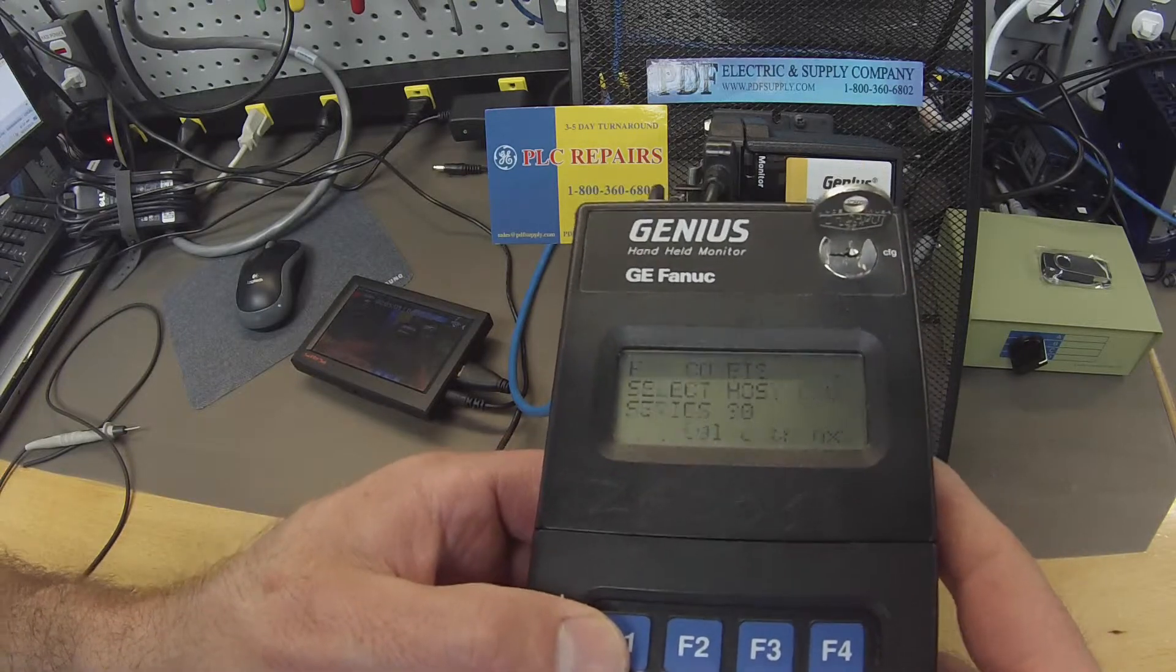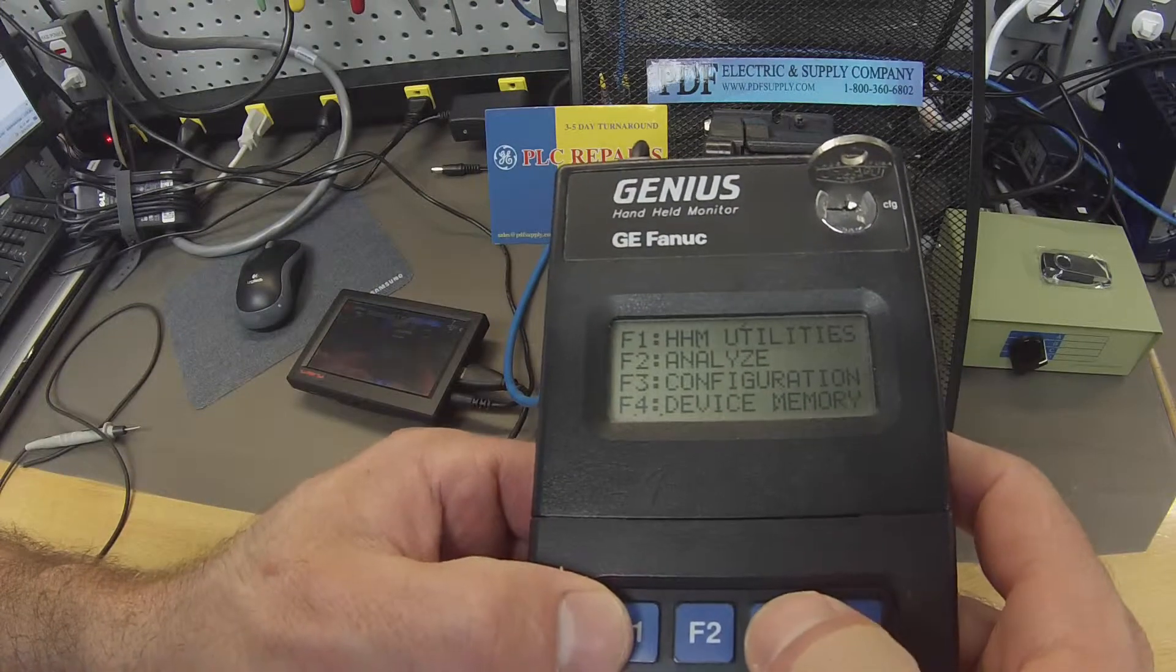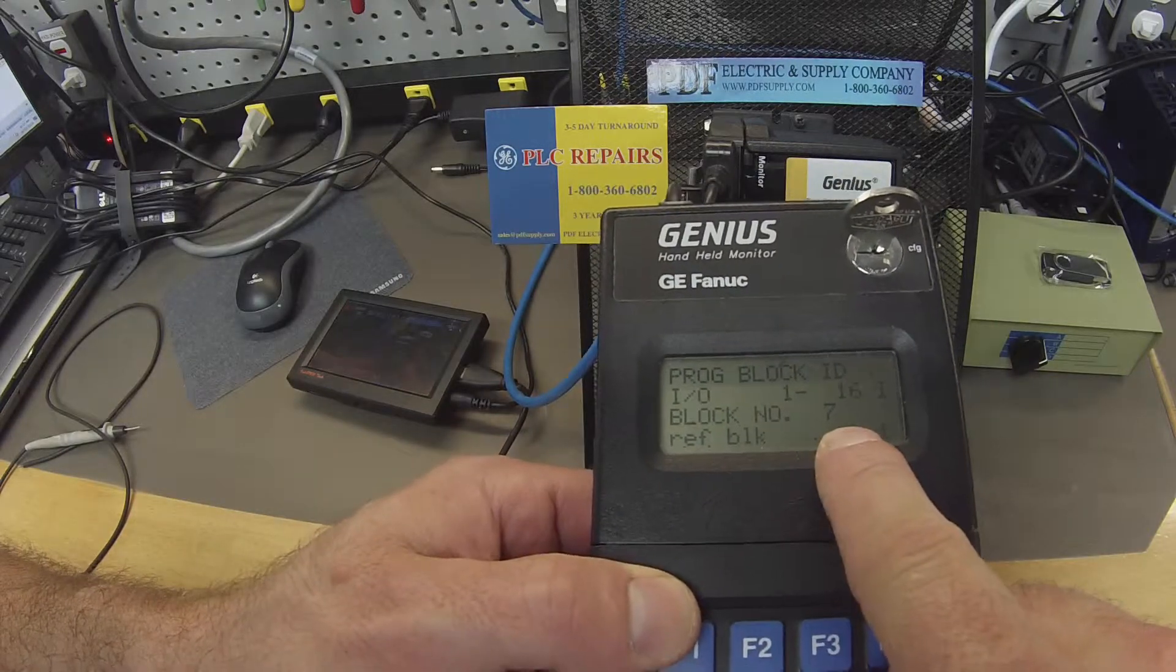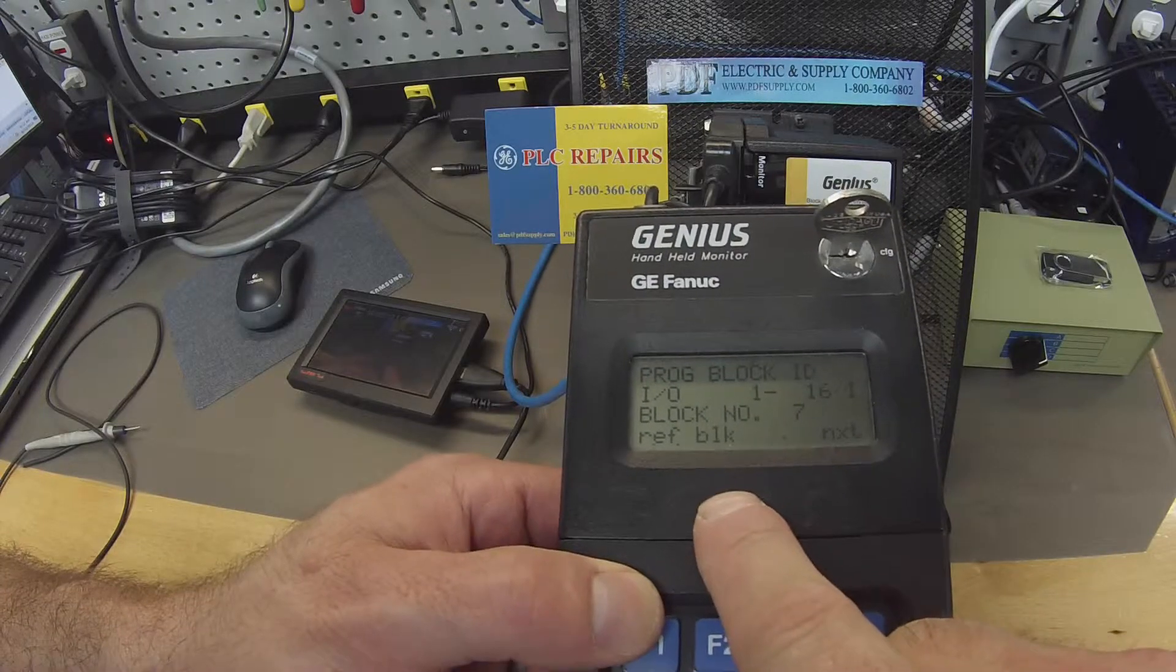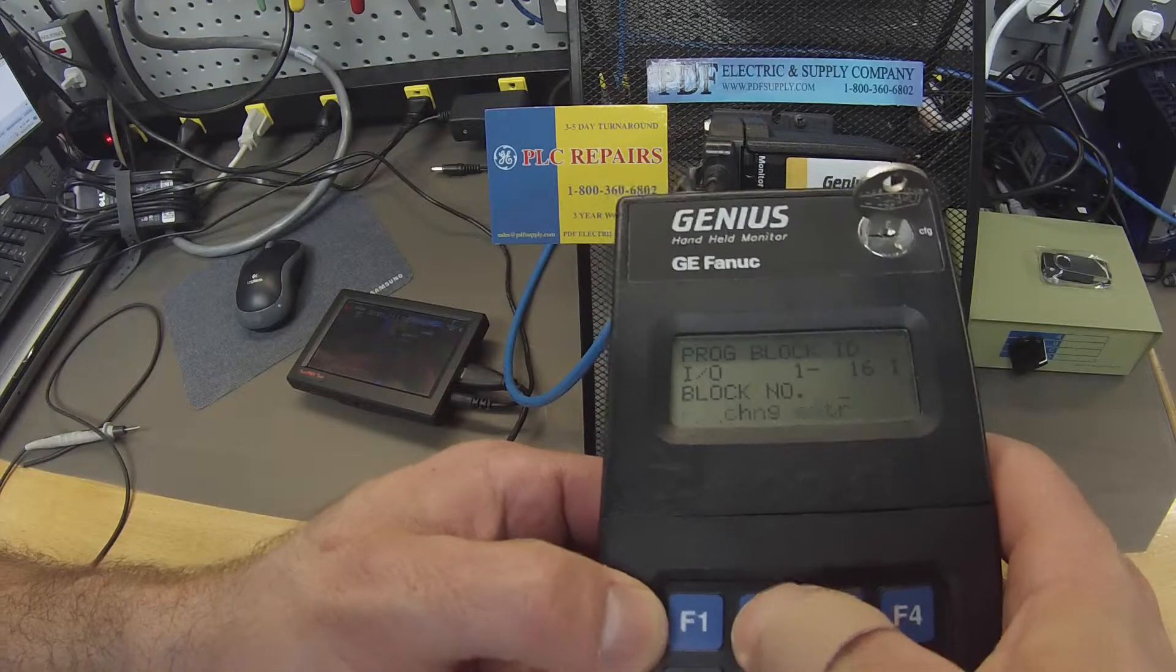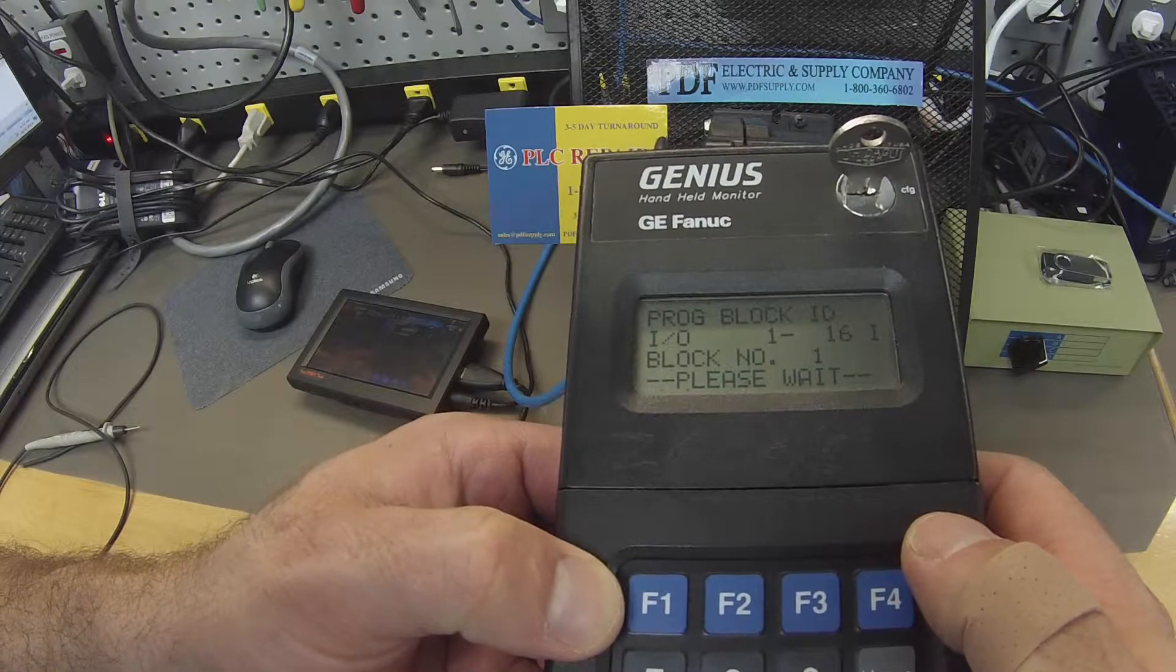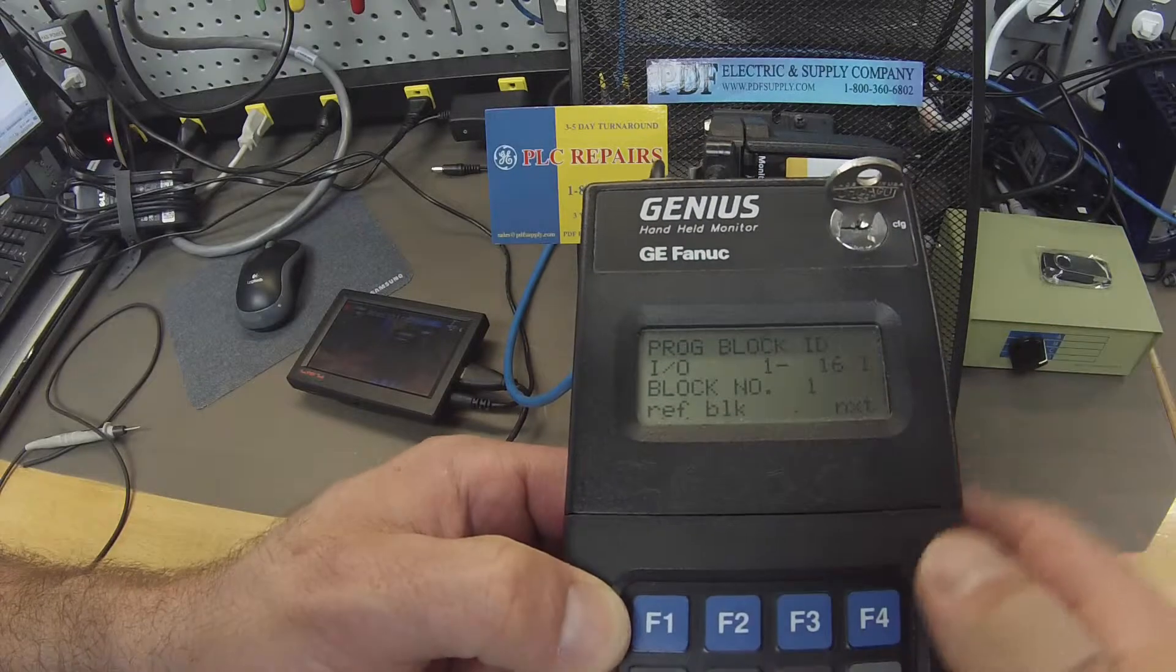I'm going to go back to home. Press home. Configuration, F3. F1, program block ID. Now, my block number is seven which does not match the block number one which is in Proficy Machine Edition. So I'm going to select block F2 and I'm going to change that to one and enter. Then once it's back to normal, it'll show you that block one is now set.